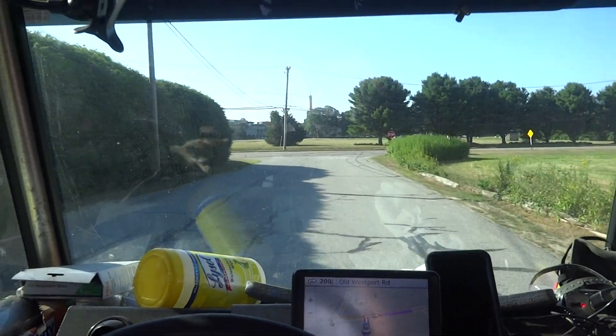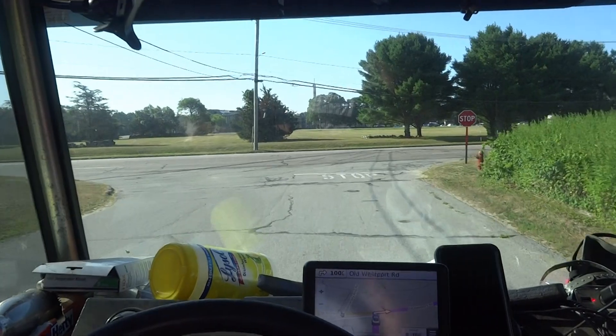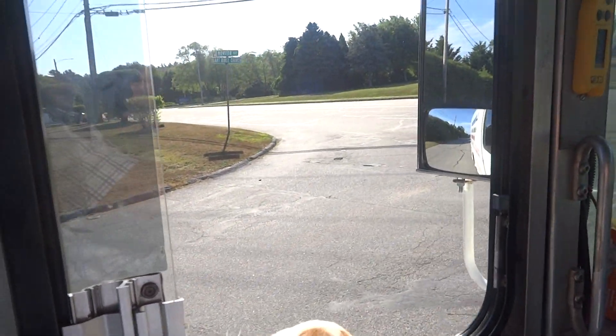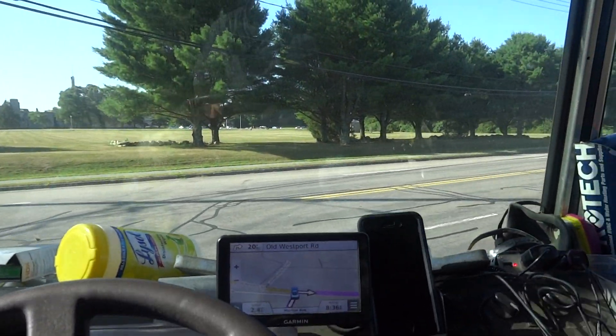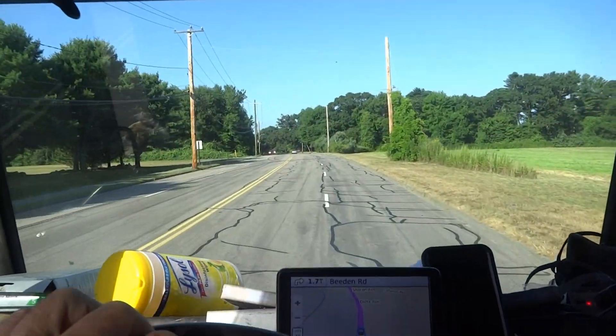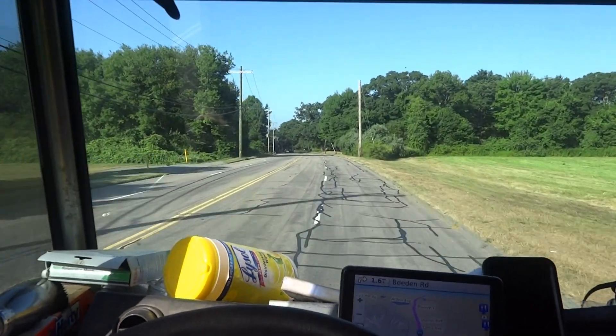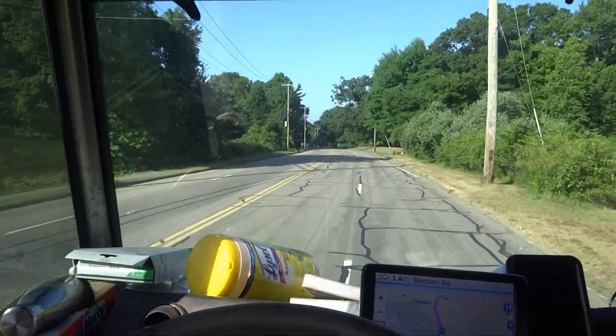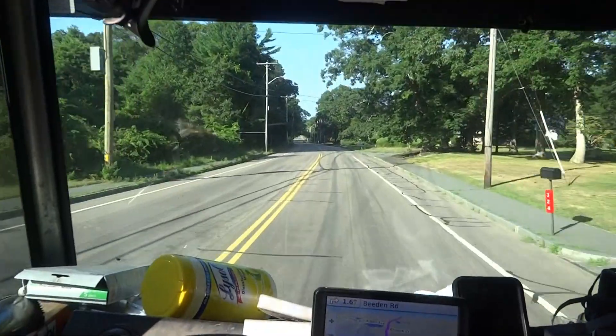If it's icing up, it's probably low on charge. You gotta let it de-ice before you check anything, because if it's iced up, you can't do nothing with it. So I told him to let it set — I'll be by in the morning, we'll check it out. I guess he watches my videos. Let's see if we can get some footage on it and figure out what's going on with the system.